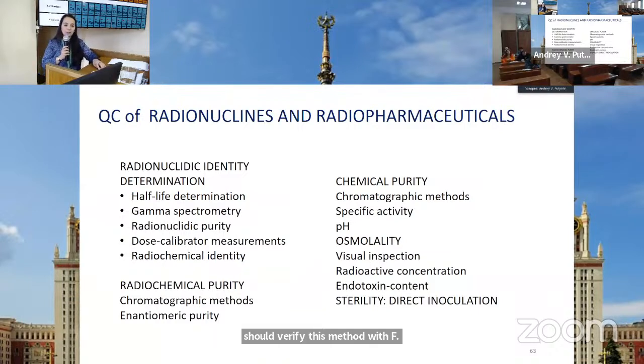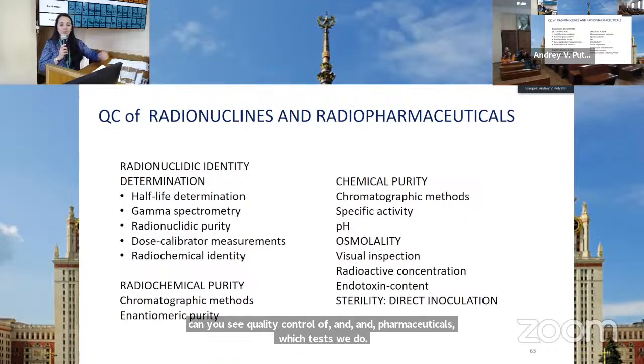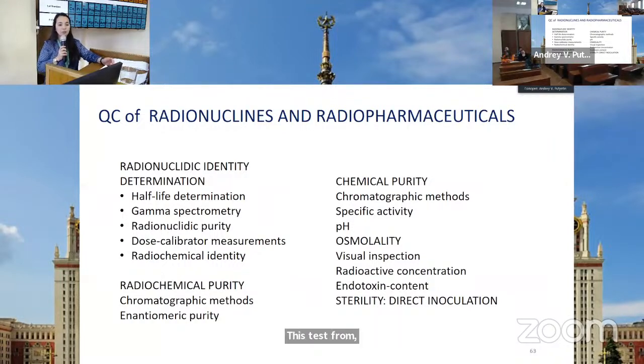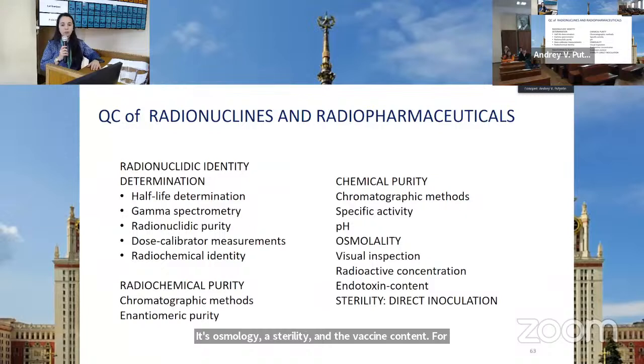Okay, quality control of radionuclides and radiopharmaceuticals. Which tests do we do? These tests are from the pharmacopoeia: radionuclidic identity determination, which is a method for half-life determination, gamma spectrometry, radionuclidic purity, dose calibrator measurements, and radiochemical identity. For radiopharmaceuticals for intravenous injection, it's osmolality, sterility, endotoxin content. For all radiopharmaceuticals: radioactive concentration, visual inspection, pH, specific activity, and we use chromatographic and radiochromatographic methods.